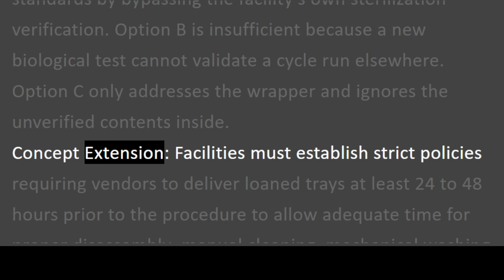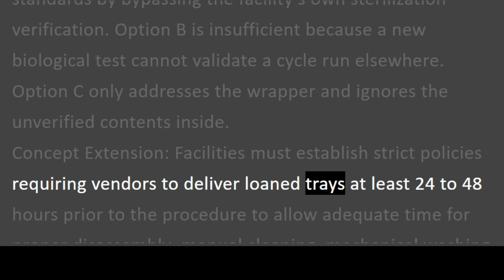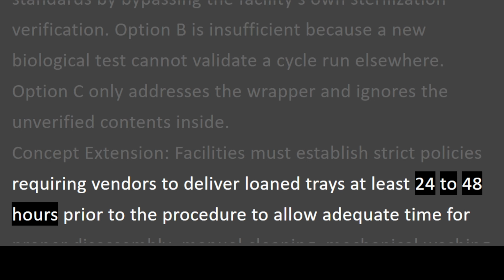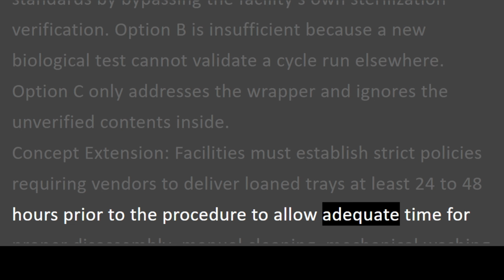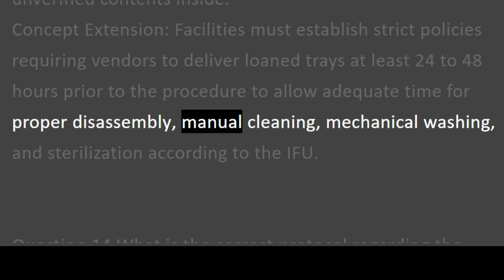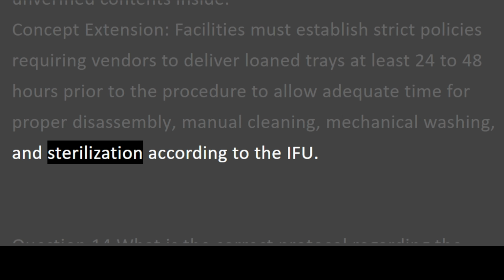Concept extension. Facilities must establish strict policies requiring vendors to deliver loaned trays at least 24 to 48 hours prior to the procedure to allow adequate time for proper disassembly, manual cleaning, mechanical washing, and sterilization according to the IFU.